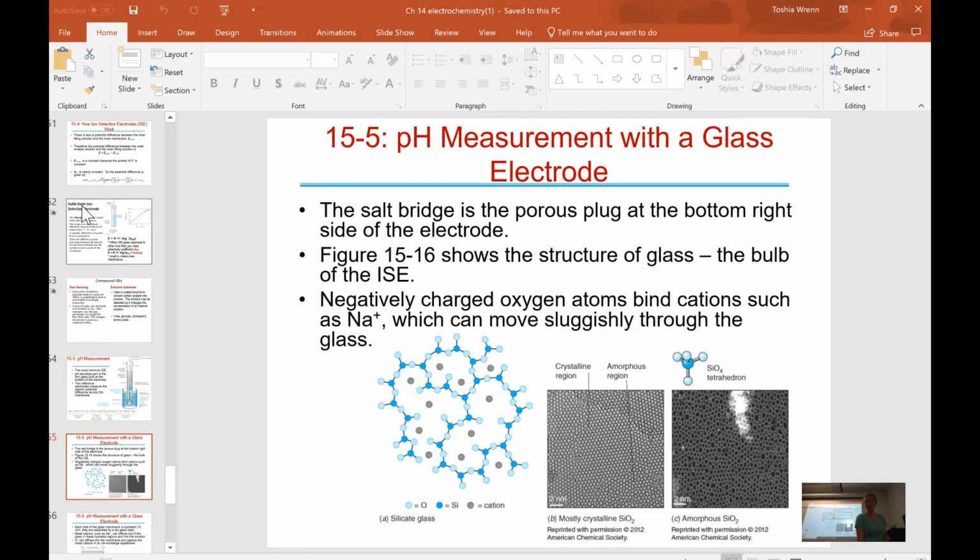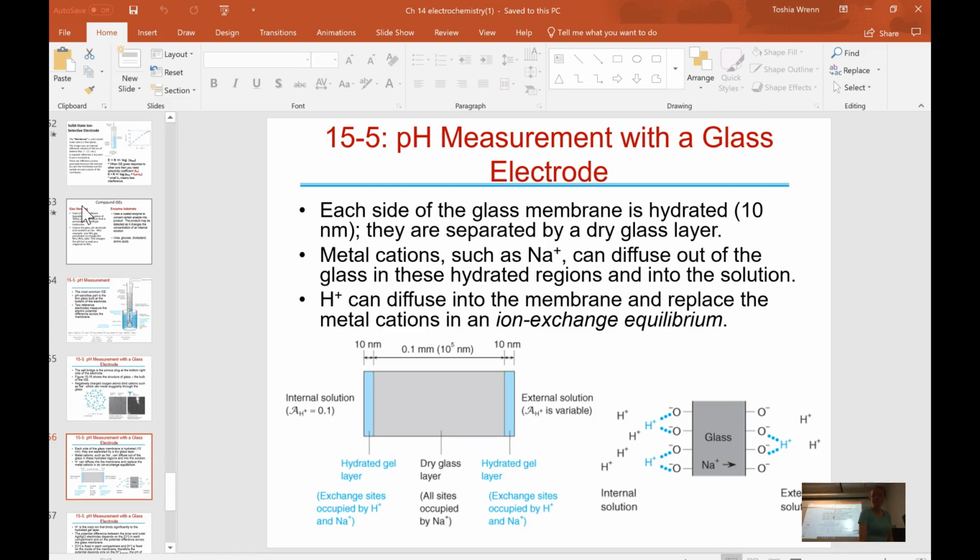And so in your electrodes, you can have these beautiful crystal cells of silica, which is an ideal dispersion of everything. Or more likely, because it's amorphous silica, you get regions of localized charge patches. Those localized charge patches are what are going to throw off a lot of your electrical potential measurements in your pH probes, because they're going to change the cell potential, that junction potential, in those locations. So again, you can get that hydration layer, which is going to affect your results as well.